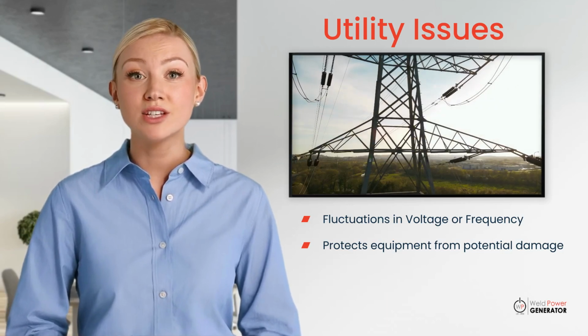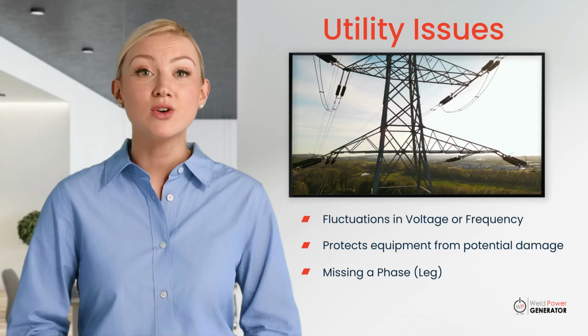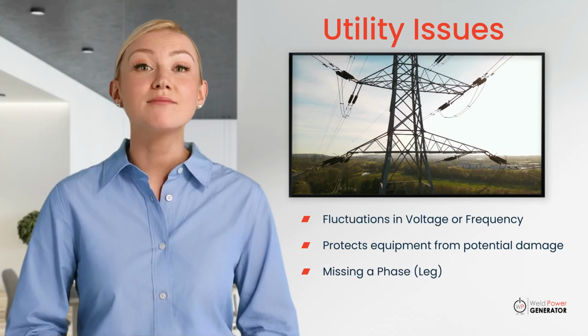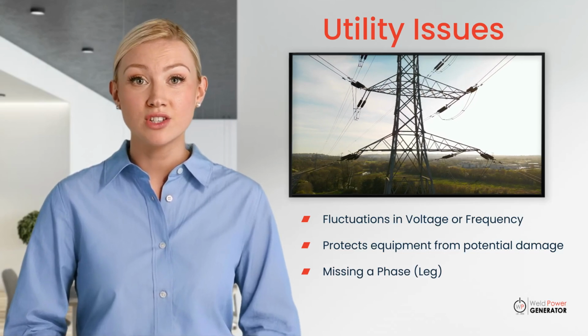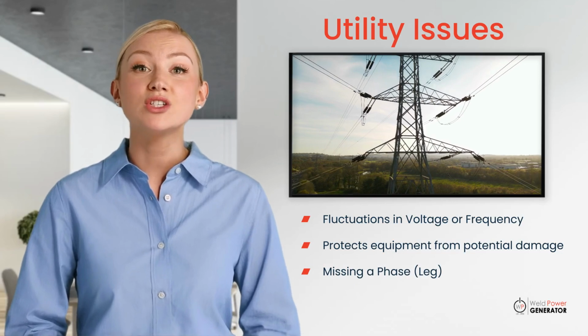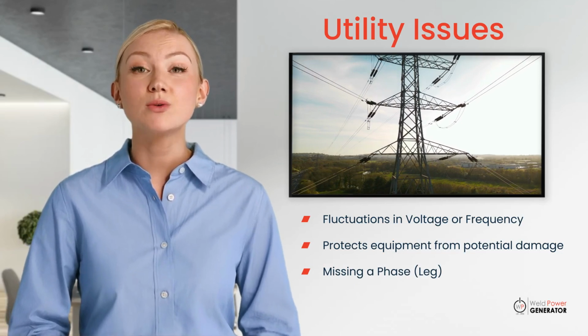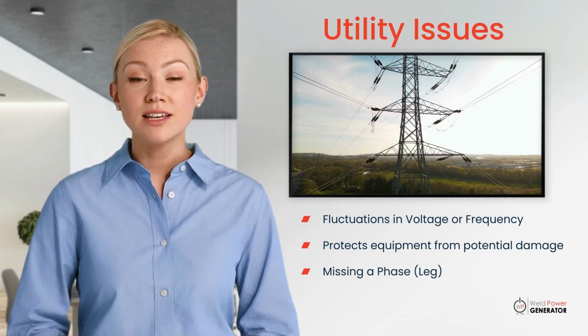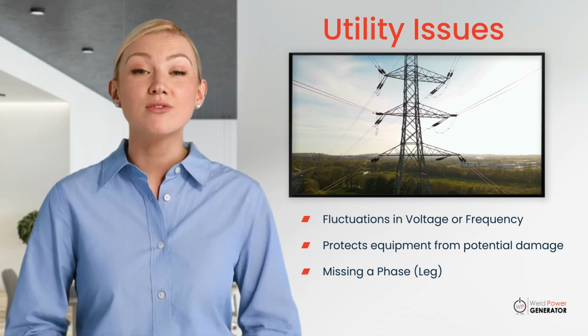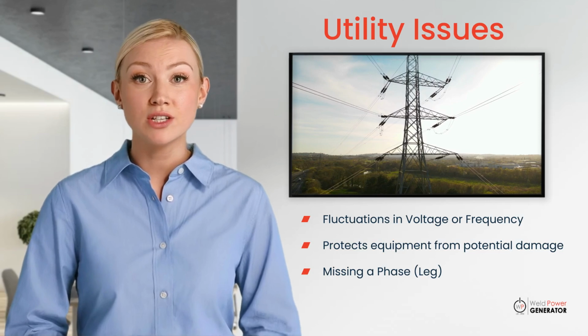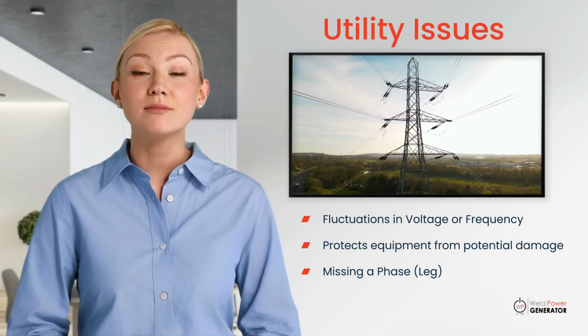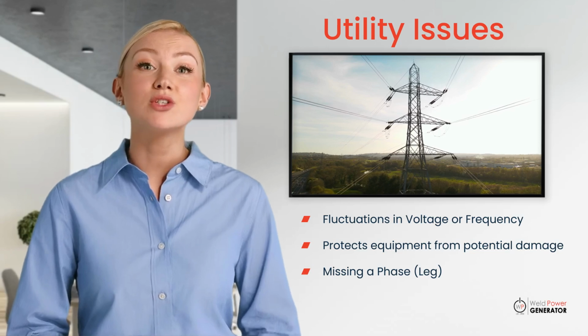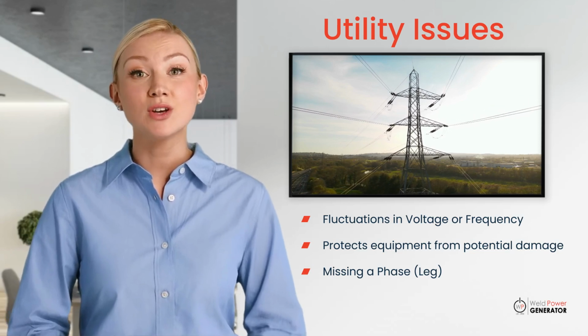In three-phase electrical systems, a missing phase or leg of power can create an imbalance that may trigger the generator to start. If one phase is lost due to a utility issue, blown fuse, or wiring failure, the ATS may interpret this as a full power outage and transfer the load to the generator. Checking for phase imbalances and verifying proper voltage on all legs can help diagnose this issue.